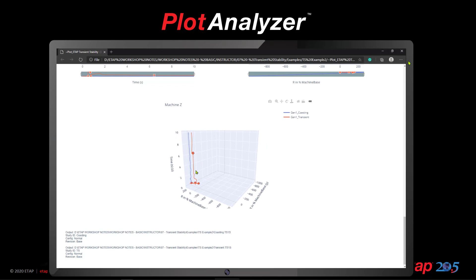When it comes to motor starting, you can essentially have many cases or applications of the plot analyzer. One of them is quickly looking at a particular motor starting event - direct across the line versus auto transformer versus capacitor bus versus stator resistor - and combining all these different methods together to quickly identify and determine what the inrush current is under every single condition, and where the voltage violations are in the system.